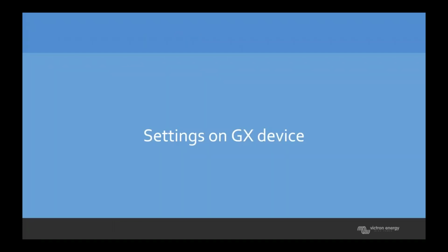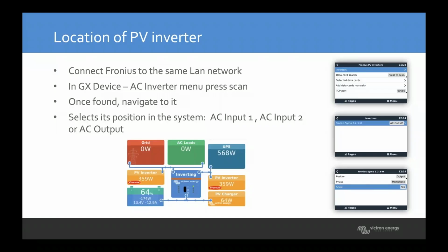Now, setting the settings on the GX device. First, if you've got a GX device, you need to set the location of the PV inverter. Head to the PV AC inverter menu on the GX device in settings. Once there, you can detect the Fronius inverter - I show you how to do this in another training available on our online training portal. Then set the position to AC input 2, or the AC output of the inverter.